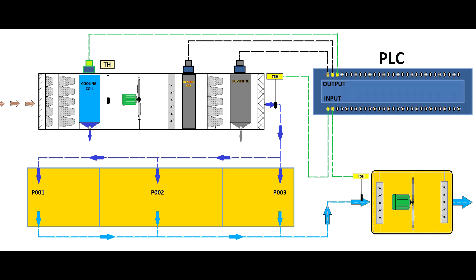Finally, I'm running the cooling heat exchanger and the humidifier. Guys, when you run the cooling heat exchanger, unlike when you run the heating heat exchanger, you will drop the absolute humidity. You actually remove moisture from the air. So when you cool your premises, as a side effect, you remove moisture from the air. And sometimes you have to compensate the loss of humidity, and that's why I'm running the humidifier. So it's really important to understand the difference between relative and absolute humidity. I will explain this in very detail, but also I have other videos that explain this in very detail.